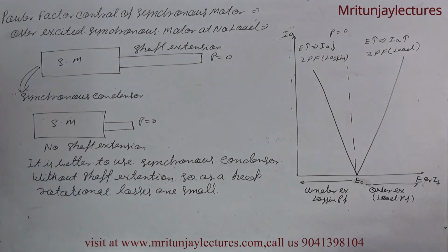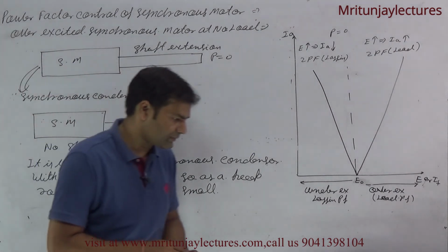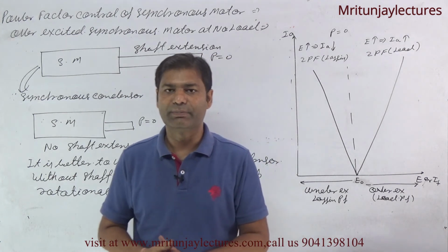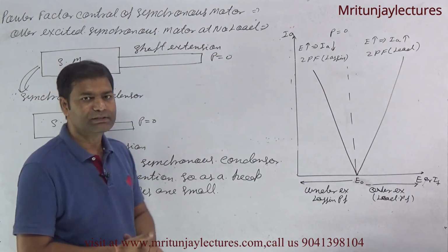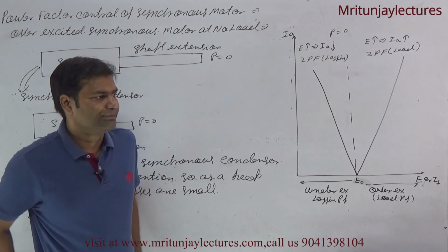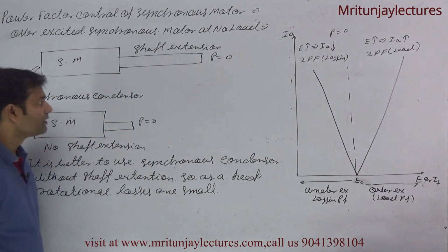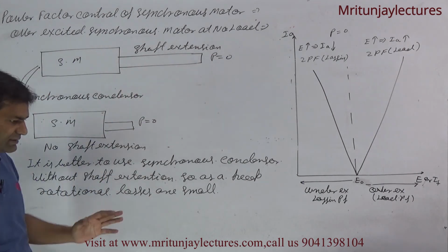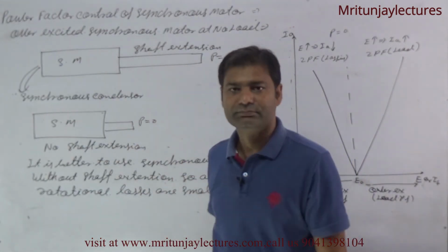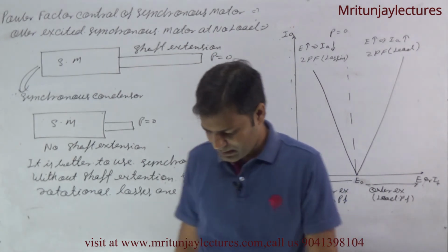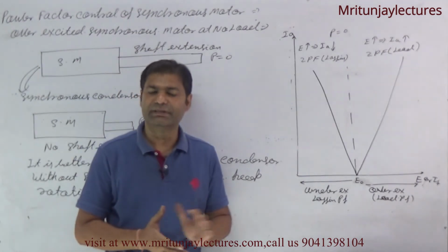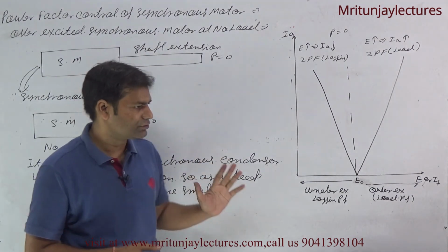Clear? If you use a synchronous condenser as a reactive power supplier, it behaves as a reactive power supplier. Then the shaft extension is removed. Why? If you remove it, then rotational losses are also reduced. So we have discussed more applications in power systems because of this.